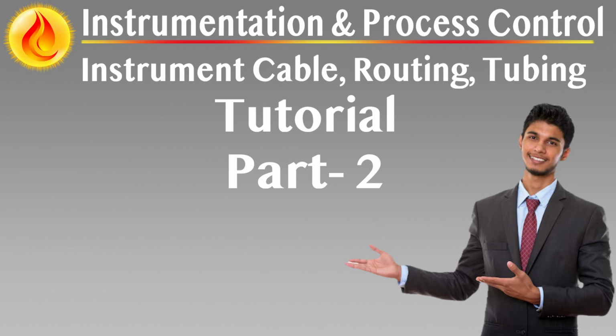Where auxiliary rooms are arranged in cellar-type configurations beneath control rooms, riser cabinets must connect cavity floors between levels, ensuring structural integrity and EMC continuity. All signal, power, and earthing cables must route through the cavity floor and enter cabinets from the bottom. Cabinets and racks must not be installed against structural walls to allow for ventilation, maintenance access, and uninterrupted cable routing. Cable gland plates are not required within these indoor enclosures.